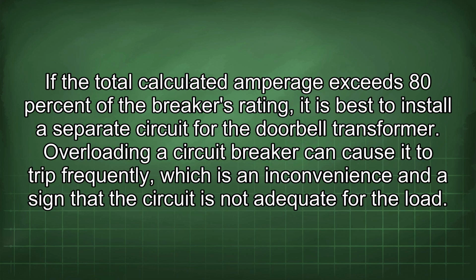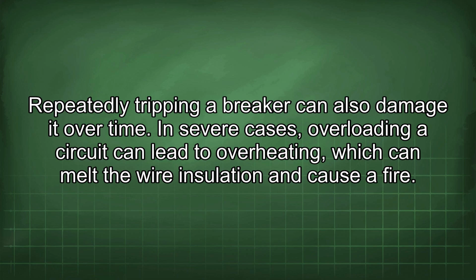If the total calculated amperage exceeds 80% of the breaker's rating, it is best to install a separate circuit for the doorbell transformer. Overloading a circuit breaker can cause it to trip frequently, which is an inconvenience and a sign that the circuit is not adequate for the load. Repeatedly tripping a breaker can also damage it over time. In severe cases, overloading a circuit can lead to overheating, which can melt the wire insulation and cause a fire.